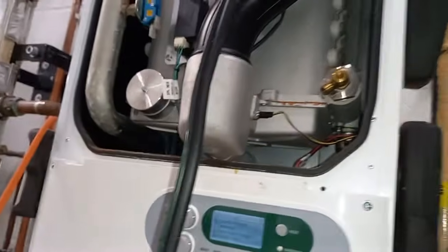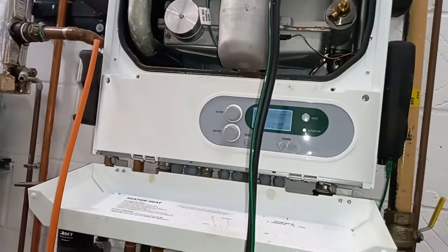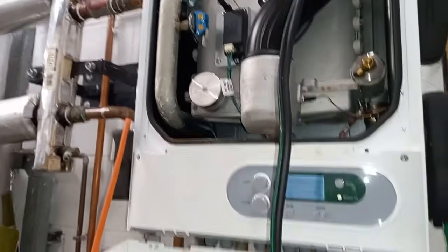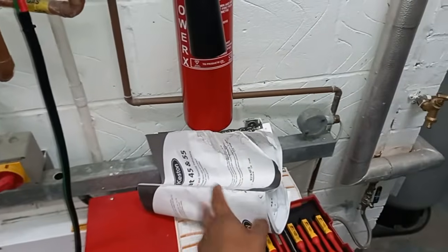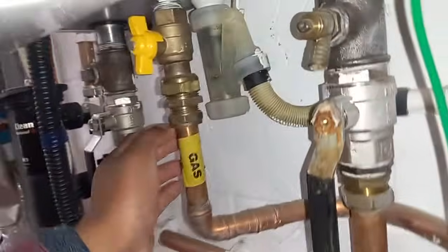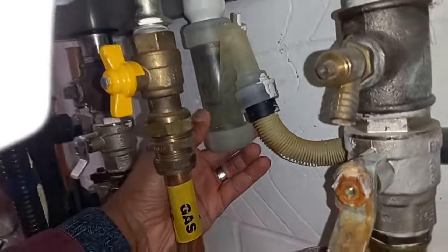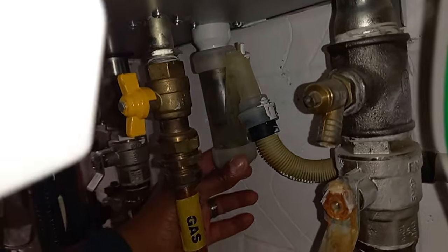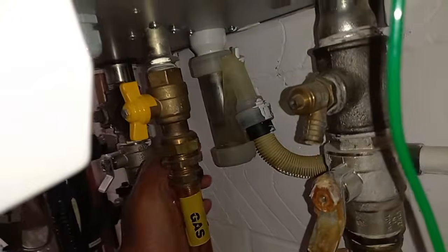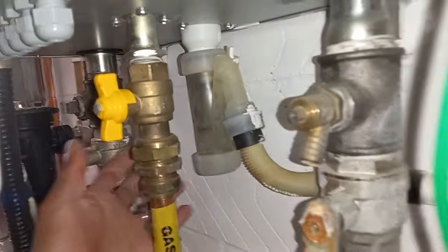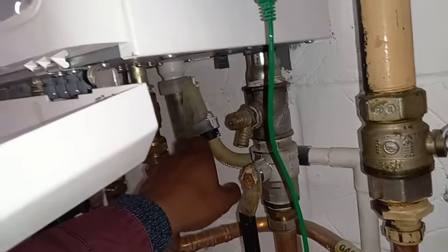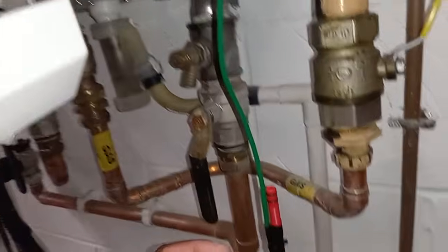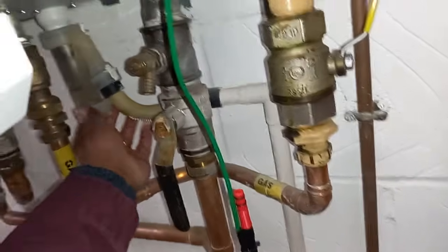So we want to do our combustion readings and we want to do our working pressure. We can do it at the same time. Ideally, you want to do these in high fire and then low. Make sure you've got your manual either on the phone or nearby to refer to. Also, it's good to have a look at the condensate trap to see, does it need clearing out? Is it fine? Ideally, you should clear it out, look for a drain, and then replenish the water. If the condition of it is great, you don't need to go and play with it, because when these get stuck, sometimes these balls get in a funny place, it can become a nightmare. But just check your condensate trap, it's not overflowing, it's not blocked, and clear it if necessary, especially if the manufacturers stipulate that it needs cleaning.